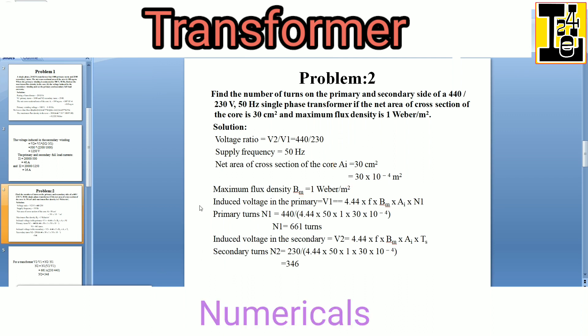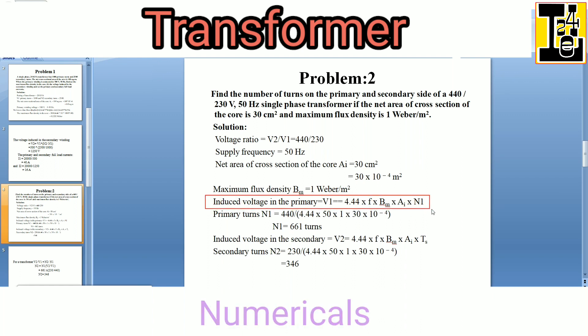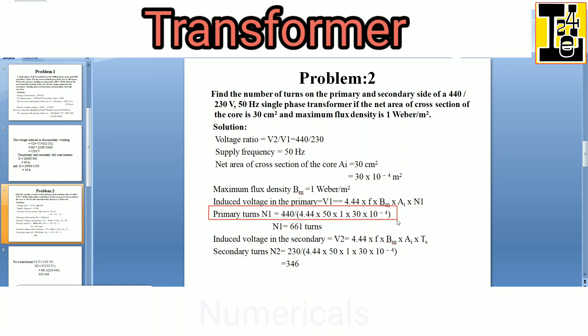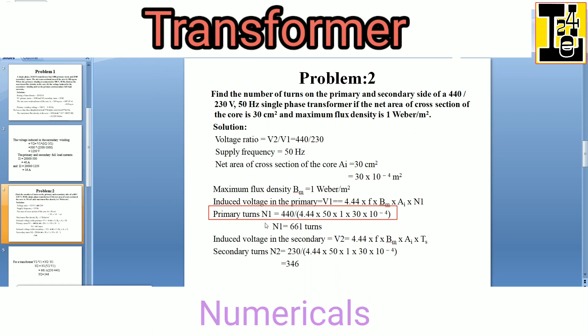Maximum flux density Bm is given as 1 Weber per meter square. The induced voltage in the primary by means of the EMF equation can be written as V1 is equals to 4.44 into f into Bm into AI into N1. So we can calculate the number of primary turns N1 as equals to 440 divided by 4.44 into 50 into 1 into 30 into 10 raised to minus 4. The number of primary turns N1 will be 661 turns.